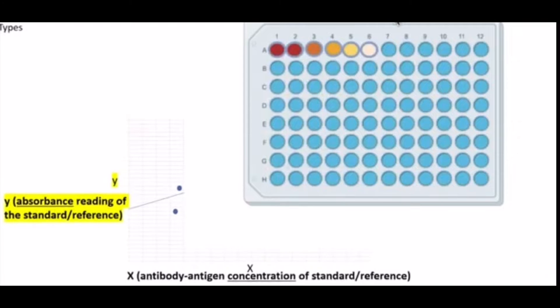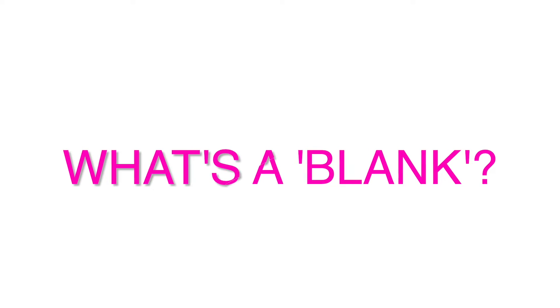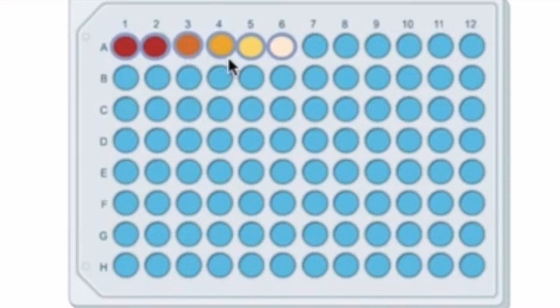A practical example for determining the limit of detection is to take, say, ten reagent blanks, so the blanks that have the same solvent as what your analyte would be dissolved in—not just water but something that replicates exactly the conditions, the buffers that your analyte would be in.